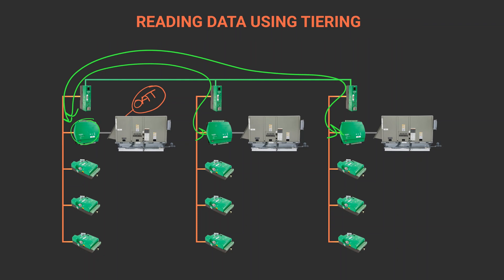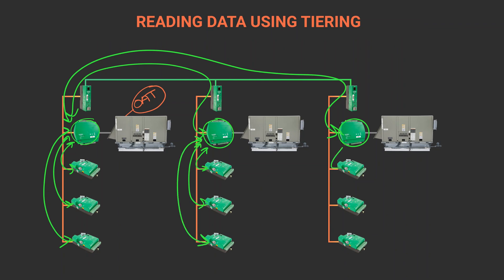Here, each air handler will request the outside air. The VAVs will then request the outside air from their air handler. Since the outside air requests from the VAVs only go to their air handlers on the same MSTP segment, the number of messages on the network between the air handlers is reduced.